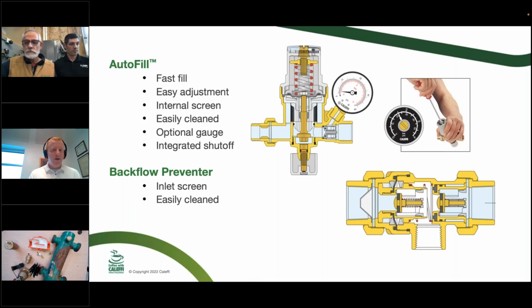And we've seen this happen quite often in leaking systems where they continue to leak somewhere where it's not noticeable, or it's under a slab or something like that. And these devices will continue to bring in fresh water. Well, that also brings in fresh oxygen and possibly debris as well from whatever your potable connection is. But the idea is this will maintain that particular pressure inside those systems. But really easy to use. You got a backflow prevention device to make sure the water goes in but not back out again. Really cool product here with our AutoFill. Very easy to set, very easy to adjust. We've got them for residential and commercial sizes.